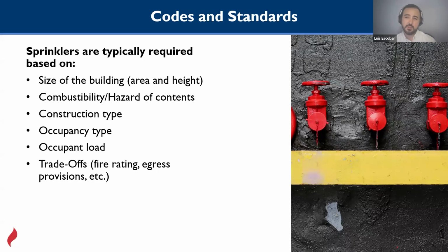For example, it's not fire sprinkler related directly, but for example, the occupancy type, construction type. It's not the same to have a type 2B building as a type 4B building. And that's going to be more related to the underground system, because the California Fire Code states what is the total demand of water that we need for each construction type. A 2B type building will have a different water demand than a type 4 building. And it depends on the square footage and all that, but as an example, not related to the fire sprinkler itself, but it supplies the fire sprinkler system, the underground piping size and demand will be defined by the construction type. So it's not only fire sprinklers, it has to do with a couple more items that are directly related to each other.